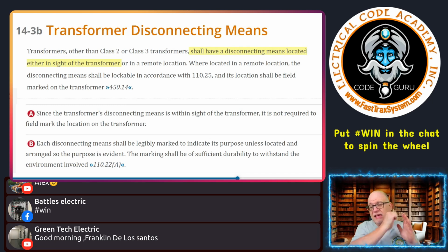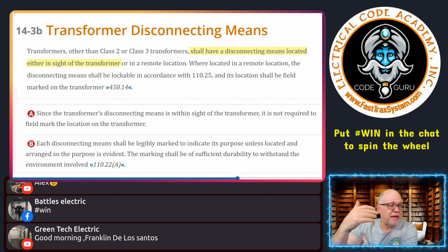So on the primary side, I need to be able to shut that transformer down and isolate it, or I can do it remotely. That means if there's maybe not enough space at the transformer, or the transformer is lifted up higher, like a 25 kVA or less unit above a suspended ceiling, maybe it doesn't behoove us to put a disconnect there. Maybe I won't meet clearances, or I have other issues, space limitations, things like that. Well, the code allows me to use a remote disconnecting means for this transformer.